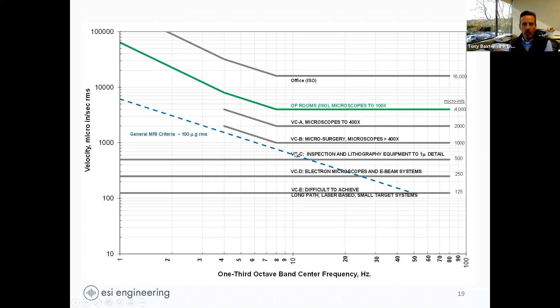So we went out, and they'd already got the building up, with the area set aside for the MRI. They never did an infill of the concrete there because they didn't know what would be needed, but they put a little slab we could measure vibration levels on. I'll show you it's not necessary — whether we measured on this little 3 foot by 3 foot slab, on the dirt, on the edge of the building, or on the footing, we're pretty much going to get the same answer.